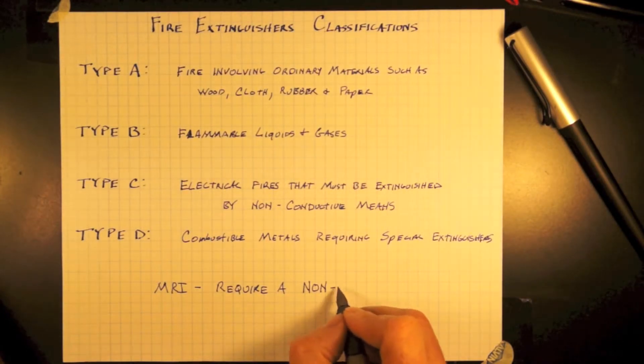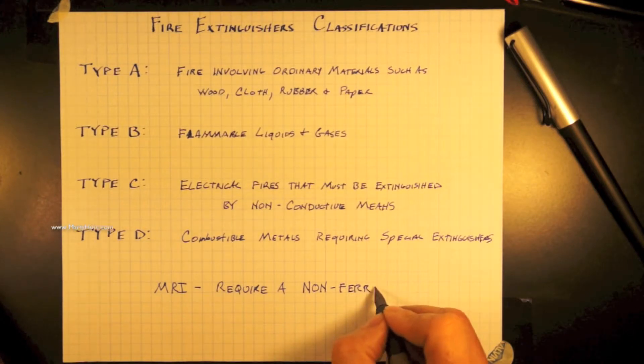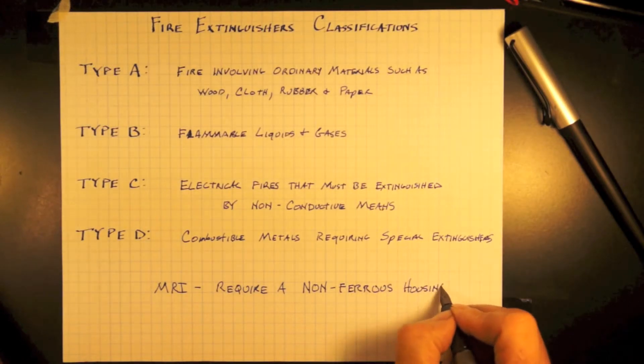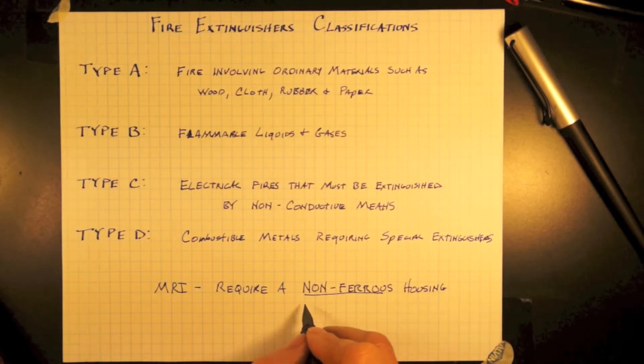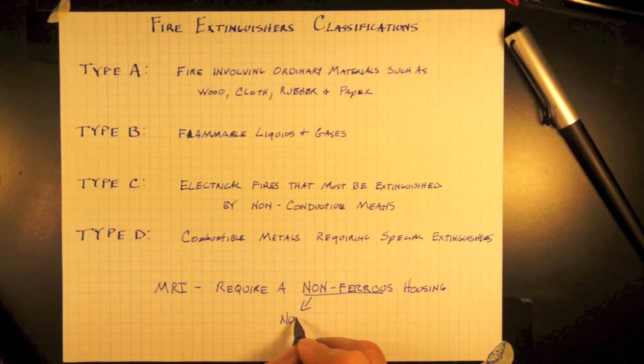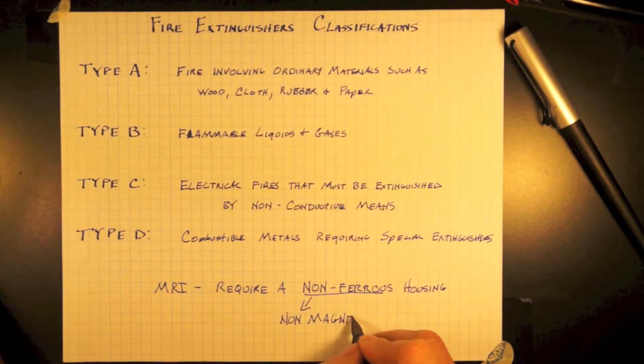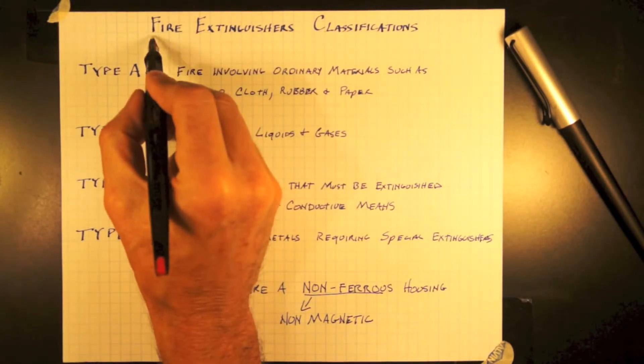Information only: there have been a number of firefighter and patient deaths due to firefighters and personnel bringing standard fire extinguishers into an MRI space. The fire extinguisher will fly into the bore of the magnet, killing or injuring whatever is in its way.